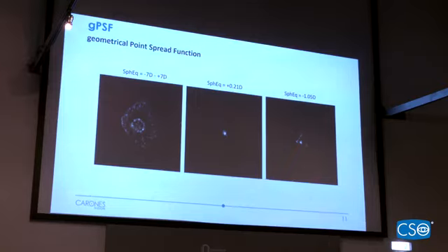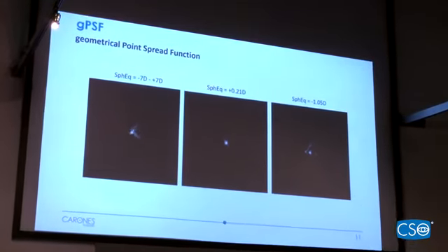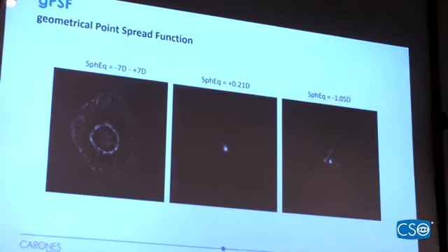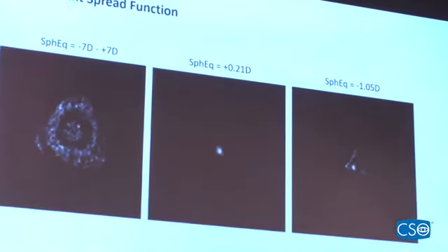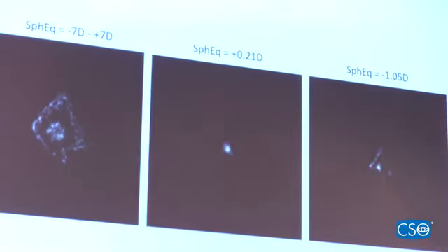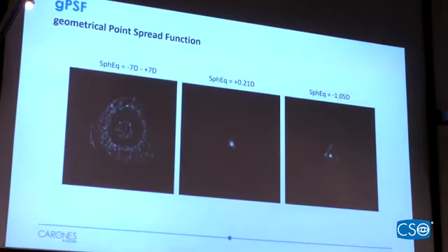And you see here really how the point spread function changes over this entire defocus curve. And you see here in the two following photographs how it is possible to define two specific points where actually the focus is more concentrated.